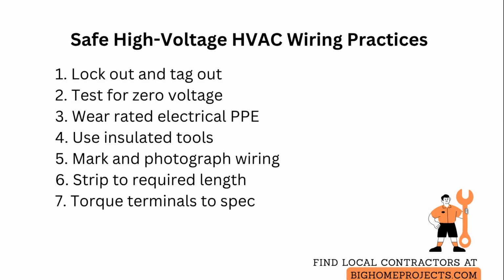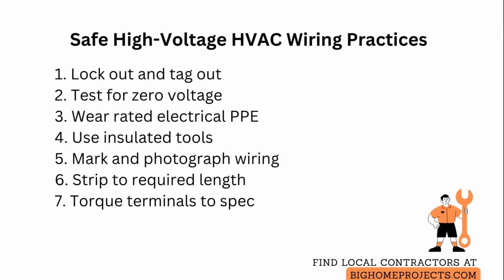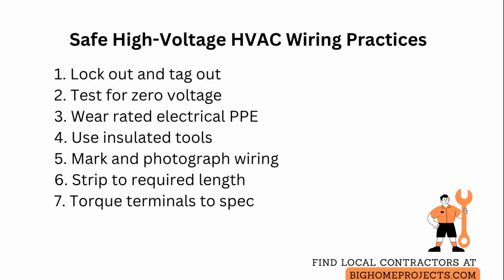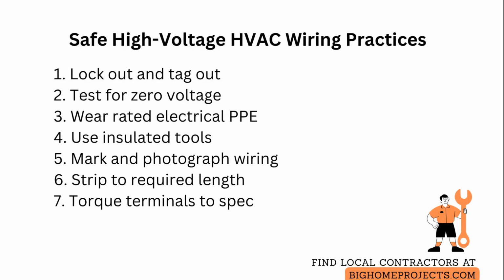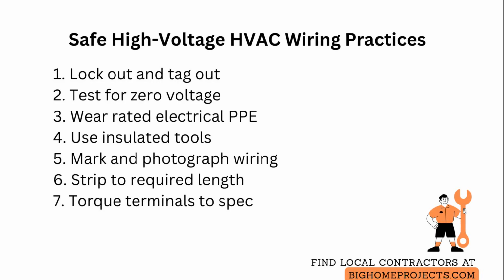After reconnection, recheck all insulation and clearances, restore power, and perform functional tests while standing clear of rotating equipment and energized terminals. If you are uncertain about the condition of insulation or terminal integrity, replace the wire or terminal block rather than attempting a temporary repair.